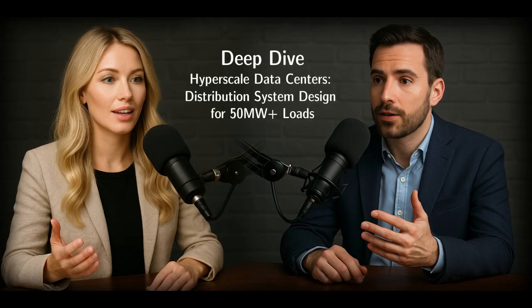And fixing it? Solutions often involve using soft-start equipment on large motors to reduce that initial inrush current, carefully coordinating any switching sequences for UPS or generators, designing the utility feed to have a low source impedance, making it stiffer and less susceptible to fluctuations, and really close operational coordination between the utility and the customer to minimize impactful events. Okay, this is complex engineering. Let's switch gears slightly to the economics. The source emphasizes looking beyond the initial build cost, focusing on life cycle cost. How does that analysis really drive the voltage level decision?